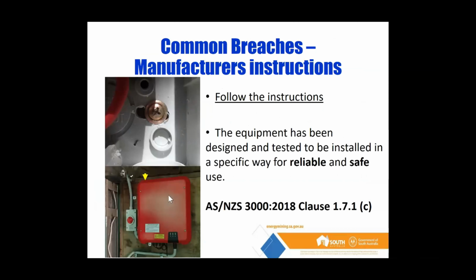Another issue that we commonly come across is guys that don't actually read the instructions. And I've got that underlined. When you purchase a product to install, that product's gone under some pretty rigorous testing and certification. The person that's designed that product and is now selling it has spent thousands, sometimes hundreds of thousands of dollars on testing and certifying it to be installed in a specific manner. If you do what this person's done in the top photo, where they've just made Swiss cheese of this IP rated enclosure and then put a PK screw there, when quite clearly underneath it is a perfectly good fixing hole that they could have used, obviously you've impaired the ingress protection of this enclosure. It's no longer what it's been designed to be installed as.